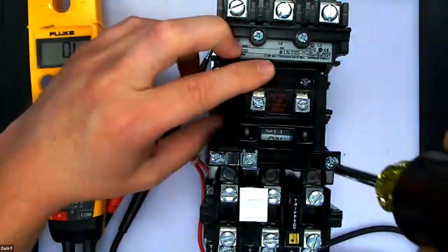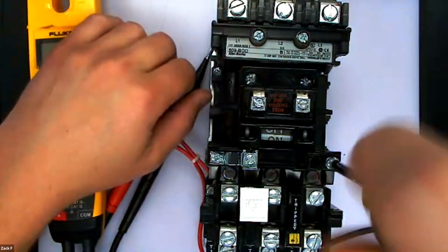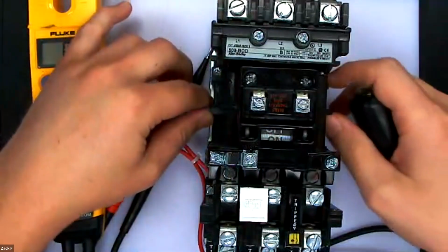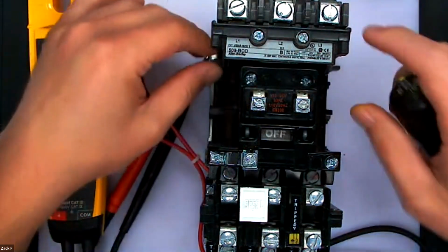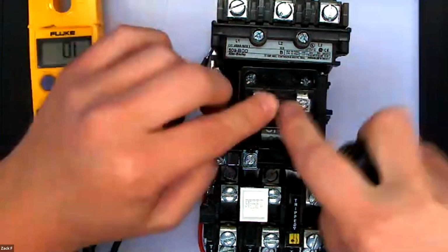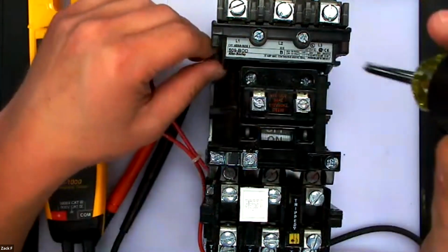And that's really all you need to know about motor starters. One piece that's not on here is something called an auxiliary contact, which comes up when we start talking about start-stop stations. They have normally open or normally closed sets of contacts, and there's one on this other starter that I'll show you. You use those normally open contacts, and when this gets energized, it keeps it closed until you hit the stop button.